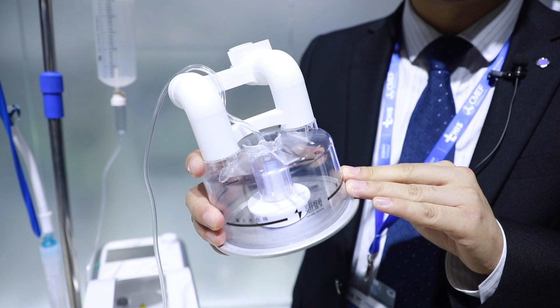A float keeps the water level at a fixed height. A heater plate warms the water, which in turn warms and humidifies the gas passing through the chamber. The gas leaving the chamber will be regulated to a dew point temperature, normally set to 37 degrees Celsius.